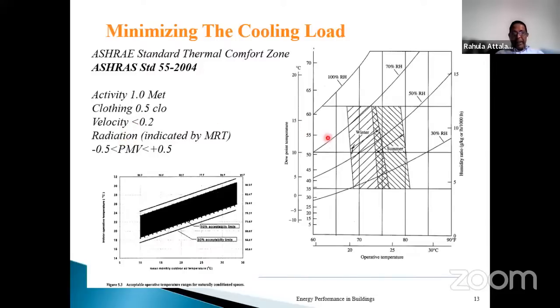The combination of these will decide the interior conditions, and based on the interior conditions, this will give a certain sensation of comfort, which is given a number called the predicted mean vote. So this hatched zone is the zone for summer conditions. The other one is for winter conditions. Let's forget the winter condition. This is the summer condition. These are the combinations of temperature and humidity where you will feel comfortable, where this vote is between -0.5 and +0.5. And standard 55 will indicate how you can get this vote of people within this band.